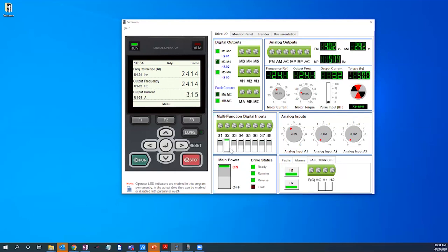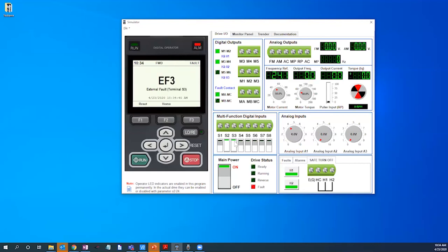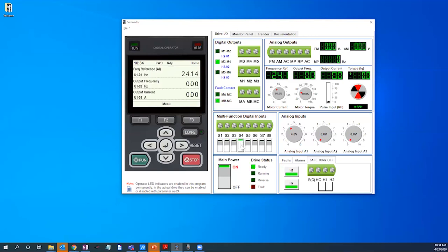While running in reverse let's go ahead and apply one of those faults that we talked about. There's an external fault applied for S3 terminal. We're going to remove the fault, power down, go to S4 to clear the fault, and start the drive again.